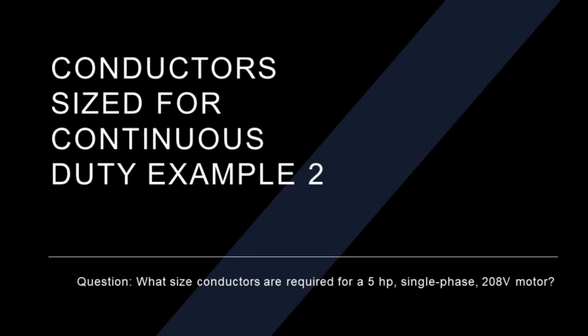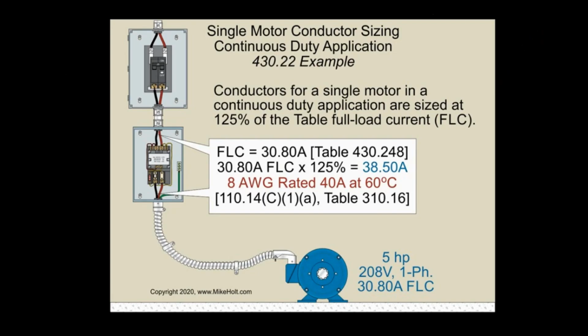All right. In doing so, a 5 horsepower motor, 208 volts. Looks like 30.8 is my FLC, right? So 30.8 times 1.25 equals 38.5 amps. Then I'm going to go to table 310.16. Let me find it. There we go. Table 310.16. I have 38.5 amps. I look to see what conductor in table 310.16 in the 75-degree column, assuming copper, I can use.